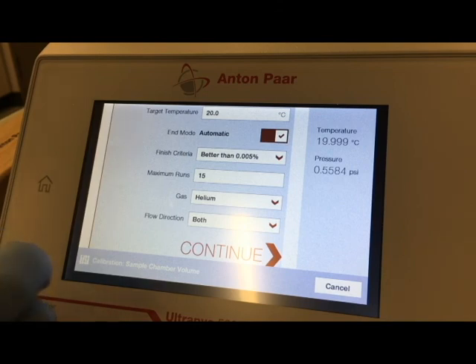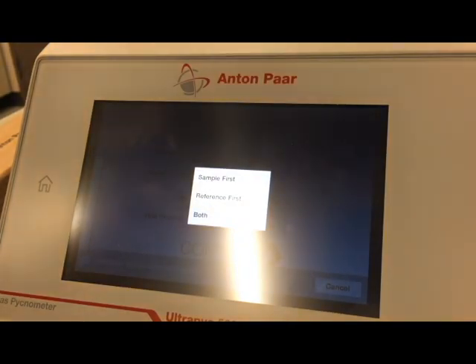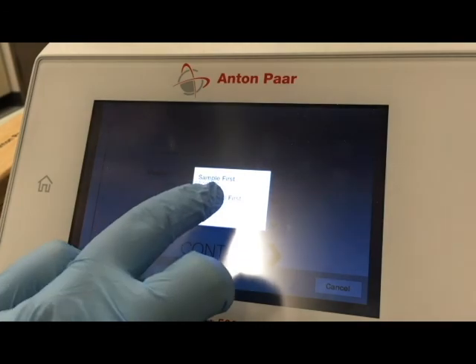Our gas is helium, and our flow direction, we have options of sample first, reference first, or both. If you have a monolith, meaning a solid sample, you want to do sample first. If you have a powder or something that is likely to splash as air is added to the chambers, you want to do reference first. If you are going to be doing both monoliths and powders in the course of your testing and you want to use the same calibration for both, choose both. For us, since we are going to be doing a powder, we're going to choose reference first.